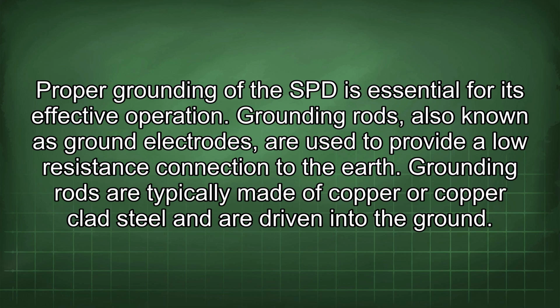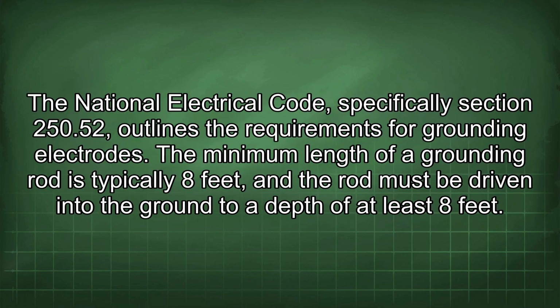Grounding rods, also known as ground electrodes, are used to provide a low resistance connection to the earth. Grounding rods are typically made of copper or copper-clad steel and are driven into the ground. The National Electrical Code, specifically Section 250.52, outlines the requirements for grounding electrodes. The minimum length of a grounding rod is typically 8 feet, and the rod must be driven into the ground to a depth of at least 8 feet.